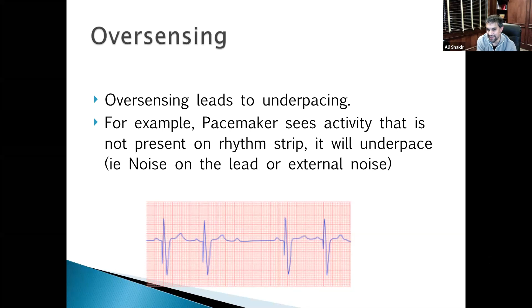So we could say, well, gee, why is it not triggering there? And it's because it must have sensed something in the ventricle. If it was under sensing in the atrium, then it would have fired in the atrium after that P wave. So we would have seen a pacing spike. Maybe we wouldn't have captured depending upon if the atrium was refractory, but then we would get a beat in the ventricle. So this is a nice example of atrial sensing, ventricular tracking in a dual chambered pacemaker. Great. Thank you, Ralph. Everybody's on the same page? We can go to the next one.